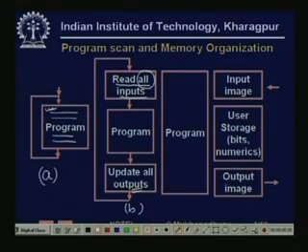And in this case it happens that typical microprocessor statement execution times run in microseconds, while with PLCs the kind of things that we are trying to control are either mechanical or thermal or chemical. So their time constants are usually so large that this subtle difference between reading all the inputs at one time makes hardly any effect. So typically for PLCs all inputs are read at one shot, at the beginning of the scan cycle. One cycle of these three steps would be called a scan cycle. After all inputs are read, the program logic gets executed. Now during the execution of the program logic, various outputs are produced.